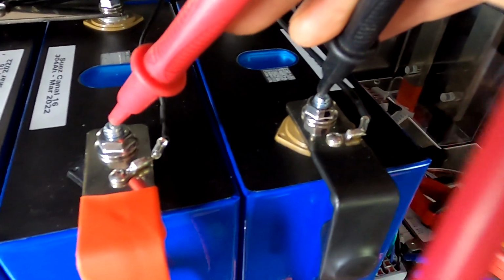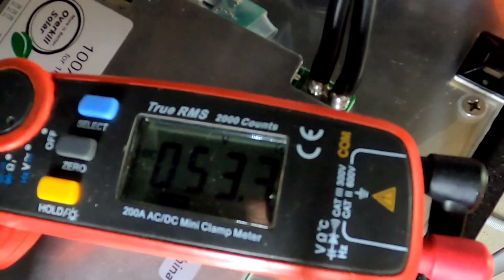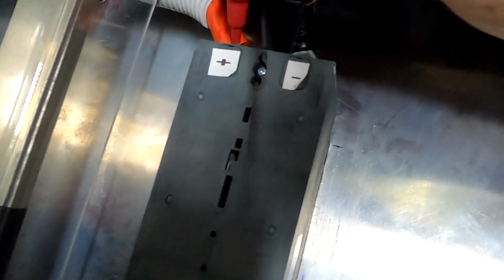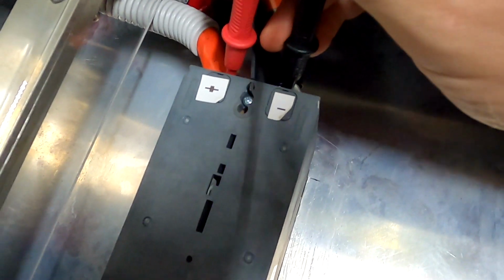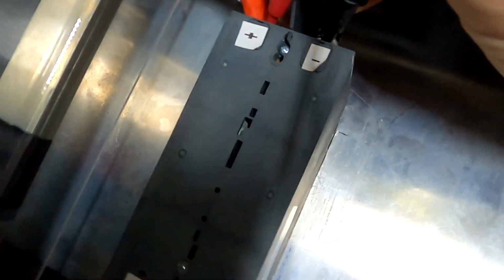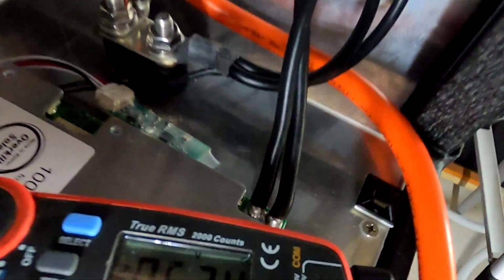So, okay, before we switch it on again, we check the voltage. 53.3 we have. And we also measure at the bus bar before we connect them, and we have 53.4. So 100 millivolt difference only.